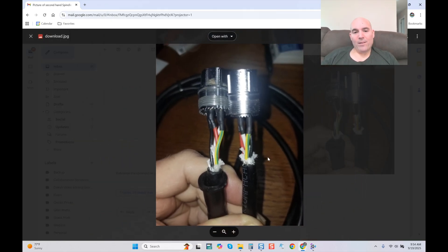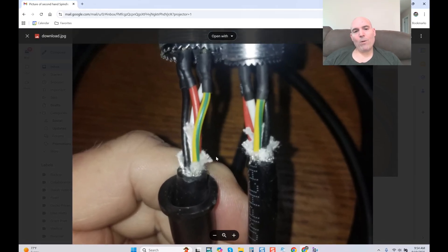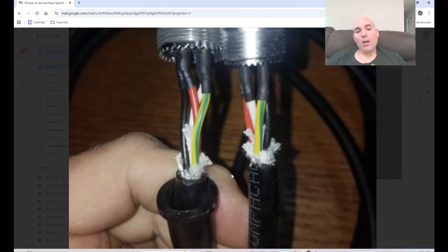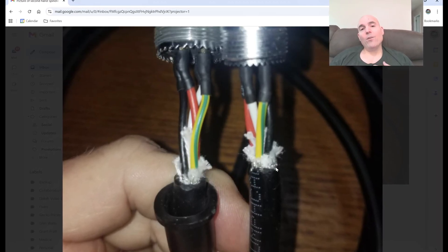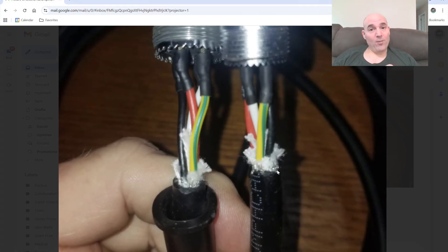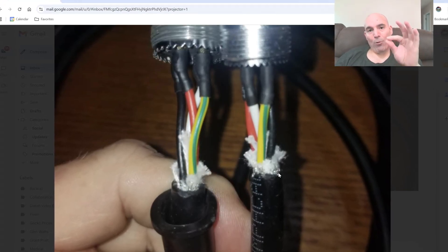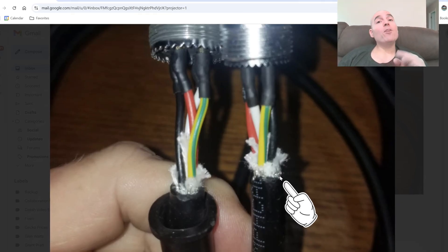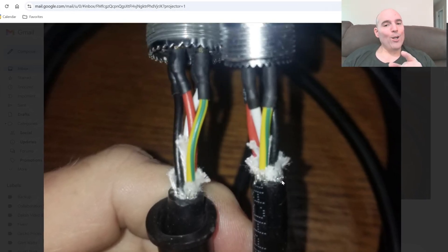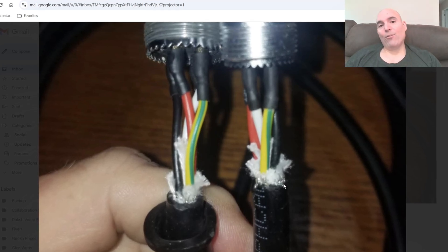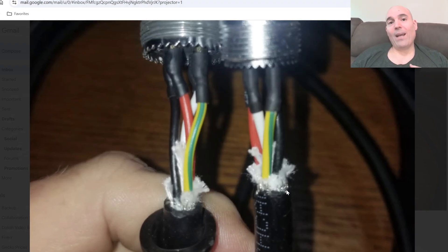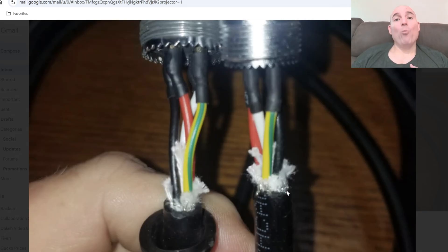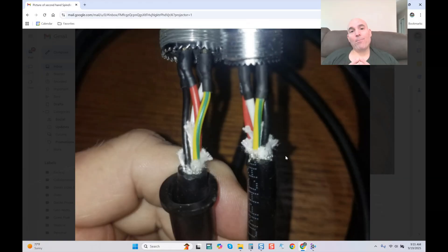Here's the cable that that gentleman sent me and you tell me where's the shield drain, guys, either end? What we do see is mass exposure of tin braided copper, which is the shield. Now anyone that's worked with tin braided copper, myself in general, will tell you those little braids of copper, the ends are very sharp—sharp enough to go in your foot if god forbid you step on them in your shop. Ask me how I know. Do you really think that protruding through the spindle cable's casing cannot go into one of those terminals, once again that's supplying power, and potentially cause a dead short? And if you guys don't believe me, trust me, it will and can happen. This is completely unsafe. This should not have any exposed tin braided copper.